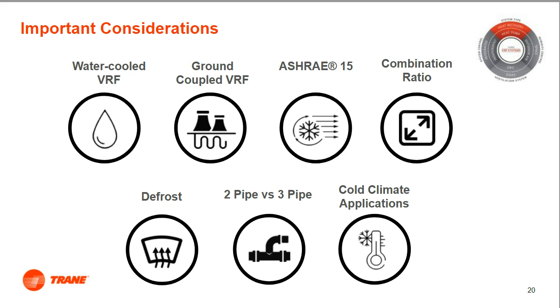Great detail must also be considered when determining the installation location of your VRF system. When systems in high humidity environments run in a defrost mode, large amounts of condensate will occur, which can lead to pooling if drainage is not properly accounted for. That's why proper condensate routing methods should be considered when installing outdoor VRF condensing units. When selecting between 2-pipe or 3-pipe heat recovery, you must take into consideration what type of building you are serving and how the specific VRF system can serve either your high-rise or low-rise zoning application. Please consult your preferred VRF manufacturer for more details about how their VRF system applies to your specific needs.